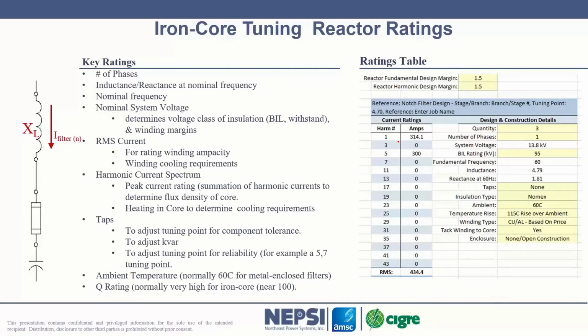Our spreadsheet tool will provide the necessary data for a reactor supplier to quote a reactor. So on a website, that tool that is used to produce the harmonic filter design, the selection of the components, will also come up with the correct component ratings for the inductor. So remember, we're pushing current. Harmonic analysis comes up with a value of current at each and every harmonic that's going to be flowing through that reactor. That reactor must be rated to carry all those components.